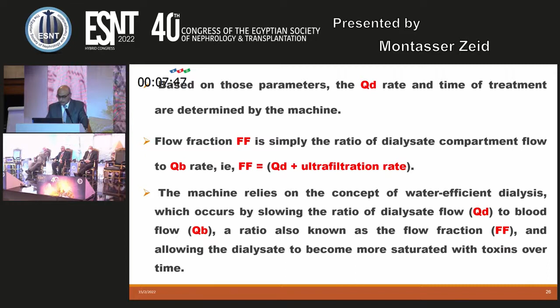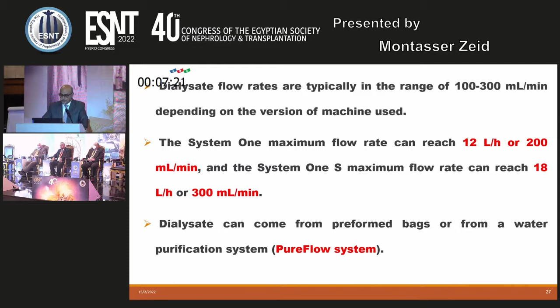Dialysate flow rates are typically in the range of 100 to 300 milliliters per minute, depending on the version of the machine used. The System One maximum flow rate can reach 12 liters per hour or 200 milliliters per minute, and System One S maximum flow can reach 18 liters per hour or 300 milliliters per minute. And dialysate can come from preformed bags or from a water purification system, which is called the PureFlow system.